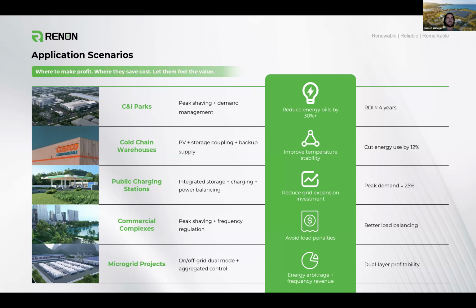C&I parks have high energy cost and demand, so there's a mitigation or arbitrage opportunity by coupling with PV—charging during the day, maybe oversizing your PV system a little so you're producing more power than you consume. That lets you charge your batteries and gives you resilience to discharge overnight. We can talk about different sizing strategies: how to make sure you have enough PV to offset consumption while charging batteries, and figuring out the right recipe overnight. If it's a three-shift facility, how do you decide the right amount of PV and power?